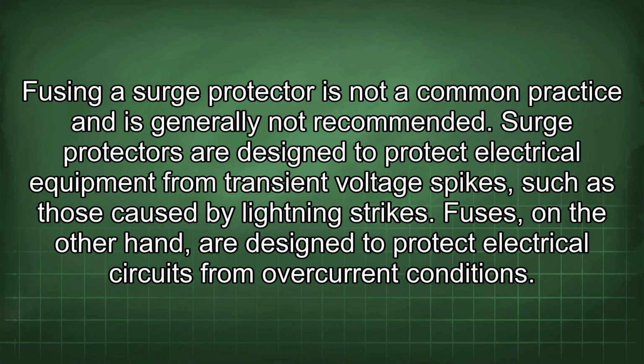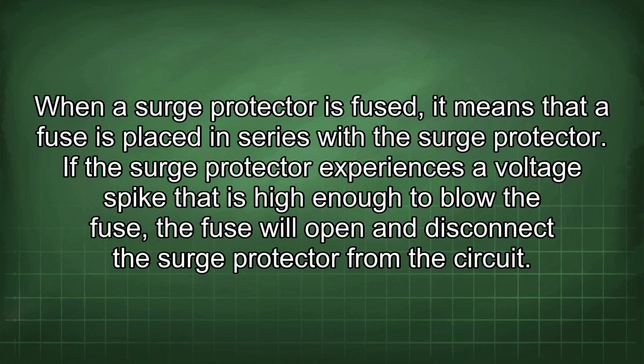Fusing a surge protector is not a common practice and is generally not recommended. Surge protectors are designed to protect electrical equipment from transient voltage spikes, such as those caused by lightning strikes. Fuses, on the other hand, are designed to protect electrical circuits from overcurrent conditions. When a surge protector is fused, it means that a fuse is placed in series with the surge protector.